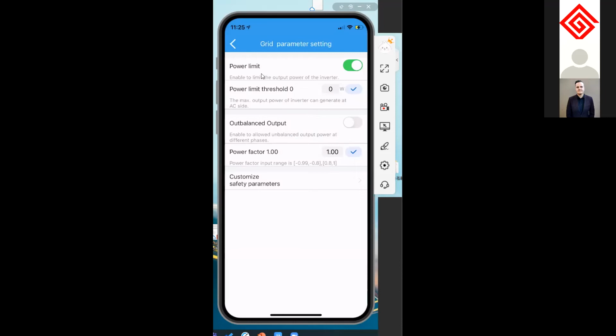On the top here, to select the power limit, you just need to click this one. Now I turn it off. Sometimes it says power limit, but sometimes it says power export control or something like that. But it means the same. Here it says enable to limit the output power of the inverter, but as it has a smart meter connected, it will not limit the output power of the inverter, but rather limit the output power past the CTs that are connected, or the current transformers. So if a smart meter is connected, this is the same as power export limit.